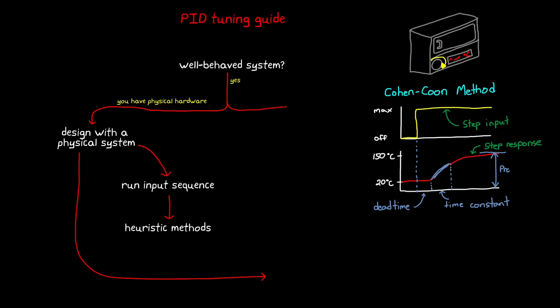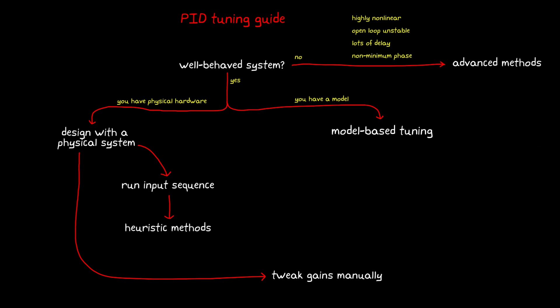And then plug those into an equation to get your initial gains. You have to be careful with the Ziegler-Nichols method on real hardware, because it requires you to get your system oscillating on the verge of instability, and that's dangerous for a lot of systems, and maybe you're not comfortable doing that. Either way, these heuristic methods only provide an initial guess. Hopefully it's a close guess, but your system may still require manually tweaking the gains to get the performance that you're looking for.